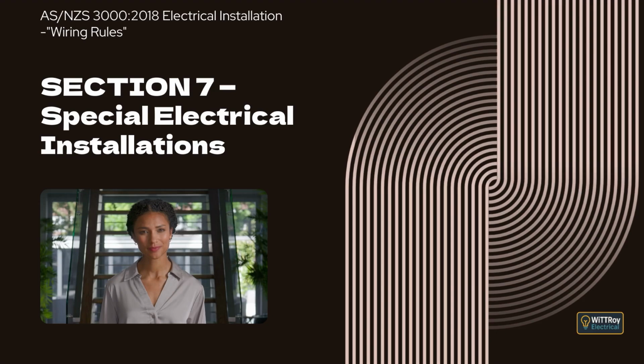Clause 7.4.2 Source of supply. This clause explains that a separated circuit must be supplied from a suitable source. The source may be an isolating transformer complying with AS/NZS 61558 so that the output is separated from the input by double insulation or an equivalent method. It explains that higher transformer ratings are permitted where the relevant construction and verification provisions are applied. It also explains that a generator output may be used where the output is separated from the generator frame, or an isolated inverter complying with AS/NZS 4763 may be used.